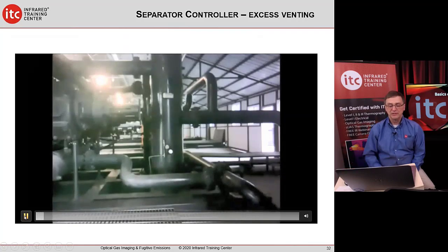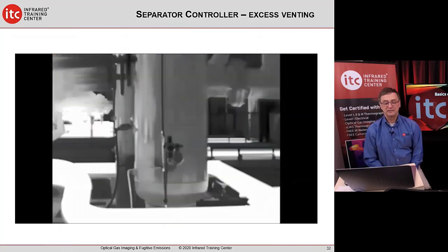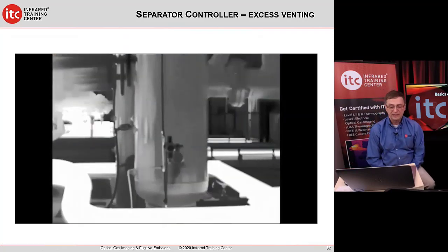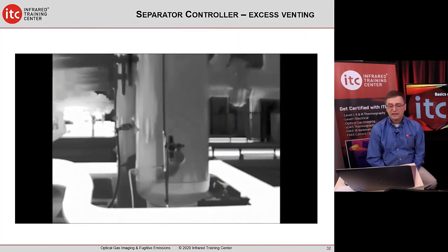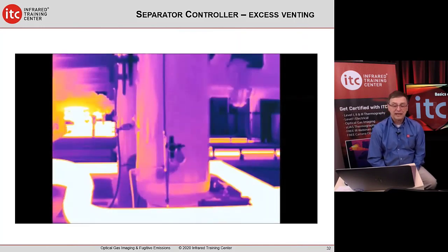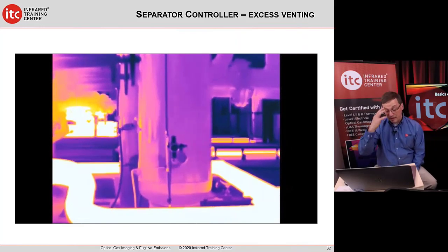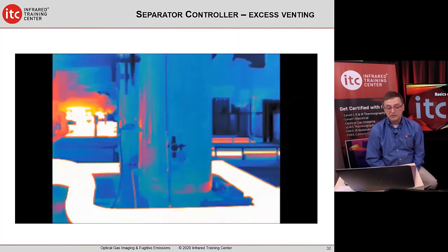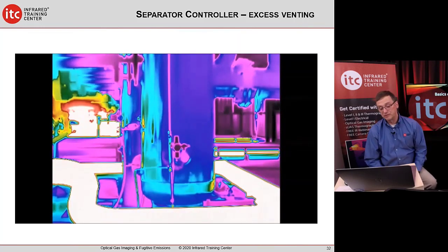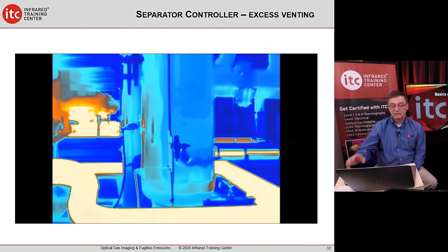Inside a compressor building, EPA recognizes that there are certain things that have to leak. And this is a level controller. This is on a separator. It can take out sand and water and other things that happen to be there. And if that valve was not able to exhaust to the atmosphere, it could not work. And so that is a level controller. So these are exempt from the regulations.